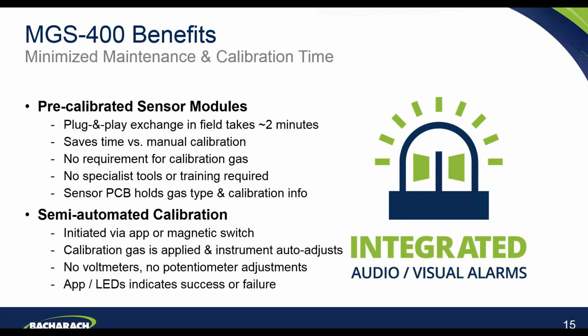Okay, so again, one of the key pain points that we identified from our voice of the customer work when designing the 400 series was the time and the expense around maintenance and calibration of gas detectors that are in the market today. So we designed the pre-calibrated sensor modules. As I mentioned, it's very much a plug and play exchange in the field. It takes a couple of minutes to do. It certainly saves time versus manual calibration, and that's particularly true if you have a site with a number of detectors installed. There is no requirement for the engineer to either purchase or carry calibration gas or regulators, and there are no specialist tools or training necessarily required to carry out the sensor exchange.